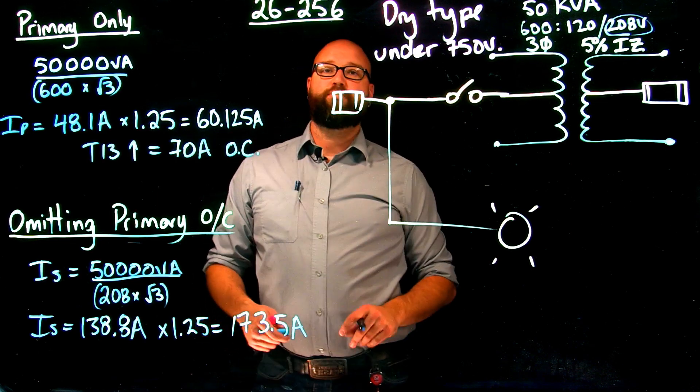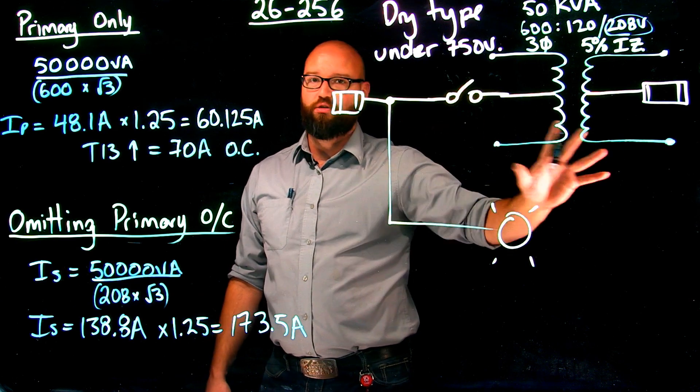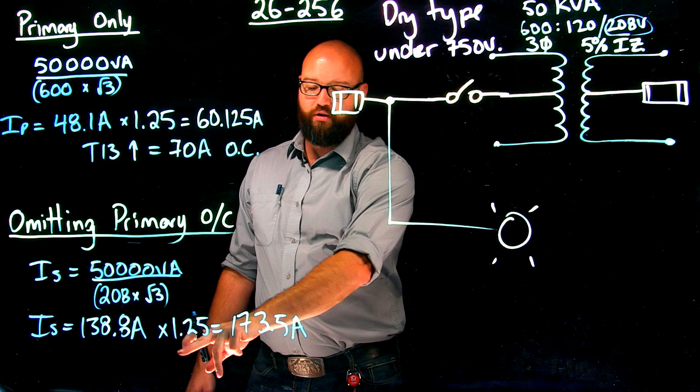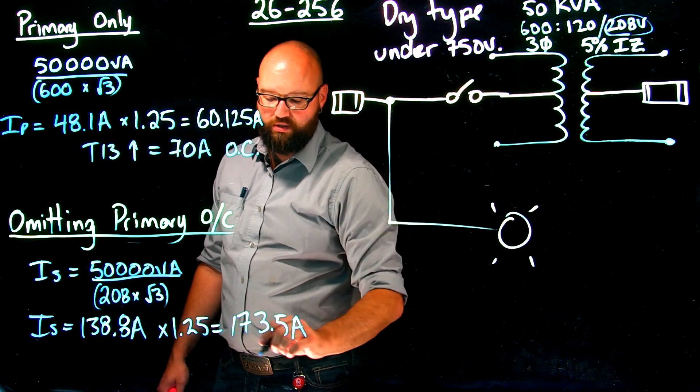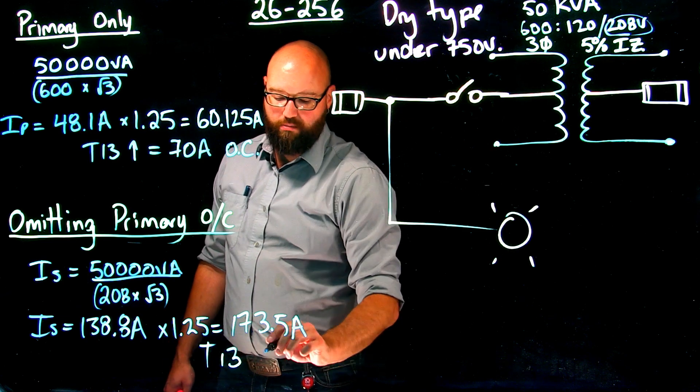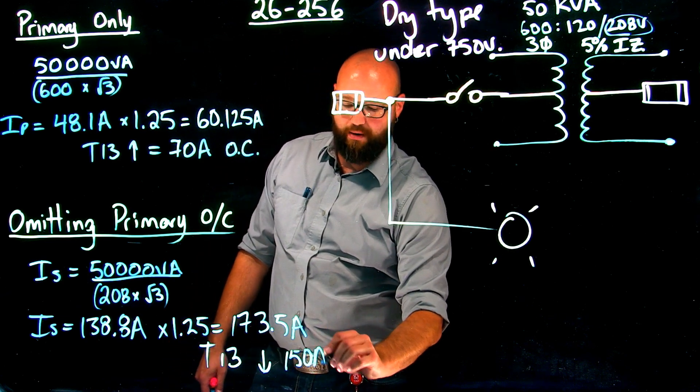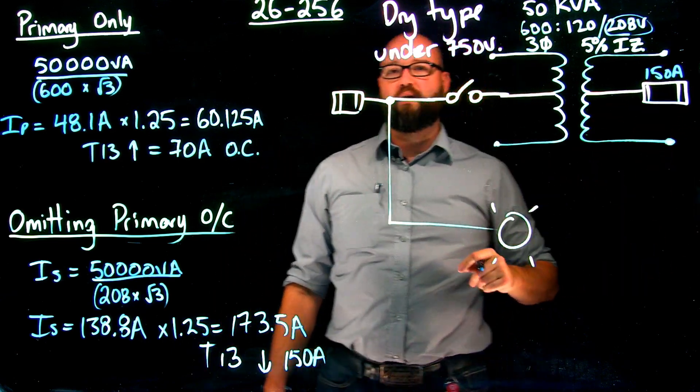Subrule 3 only applies to primary protection only, so not this situation. My secondary, I am not allowed to exceed 125% of my rated secondary. So we end up 173.5 amps. Table 13, we must go down, and we are going to choose a 150 amp overcurrent. And again, not specific to fuse or breaker.